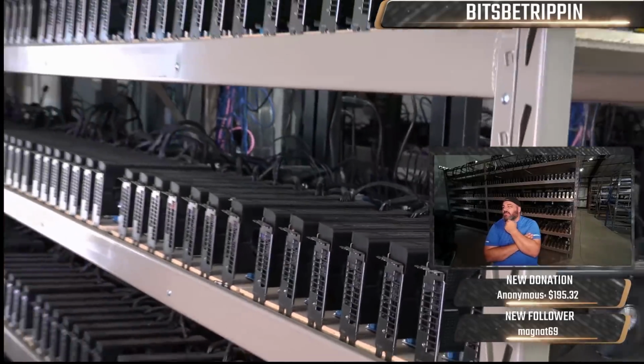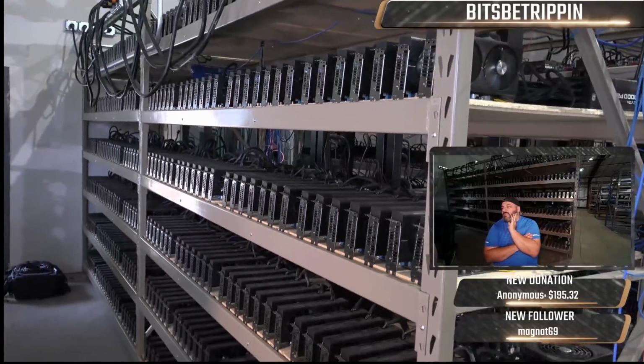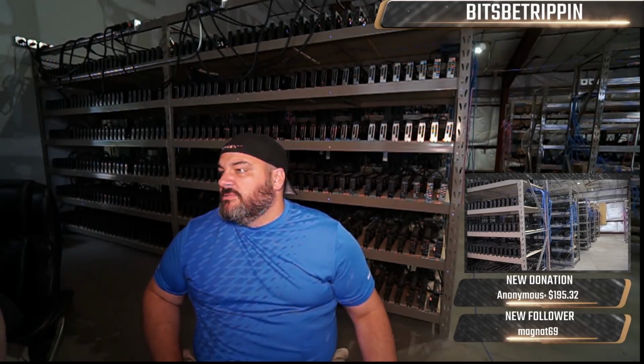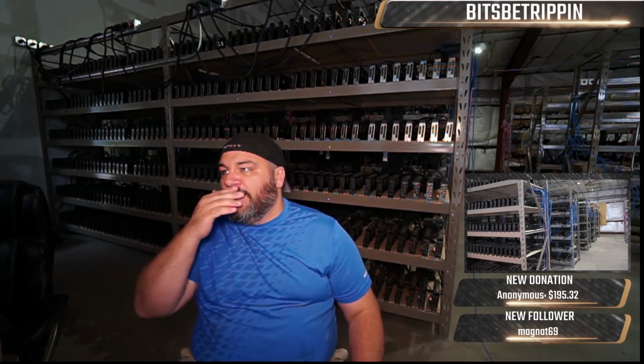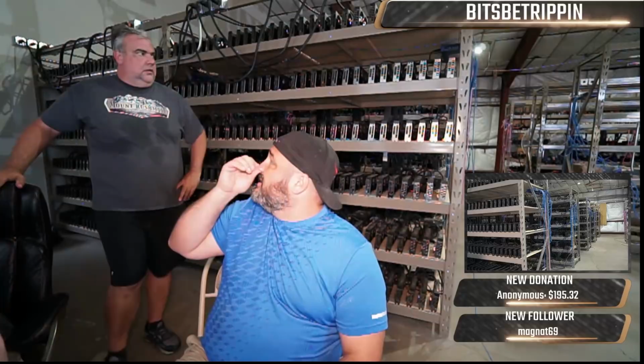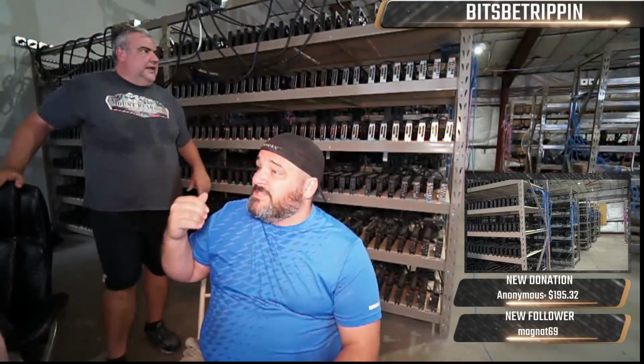Seven for AMD. So yeah, 7 across the board, both AMD and NVIDIA. Yes, those are all managed PDUs, and you'll see most of them had the network cable plugged into them. Every once in a while, when we got here, 2 PDUs on one side had popped the circuit. They're running about 27 amp when they're running the hardest on a few of them. I saw a few of them setting at 27 amp.